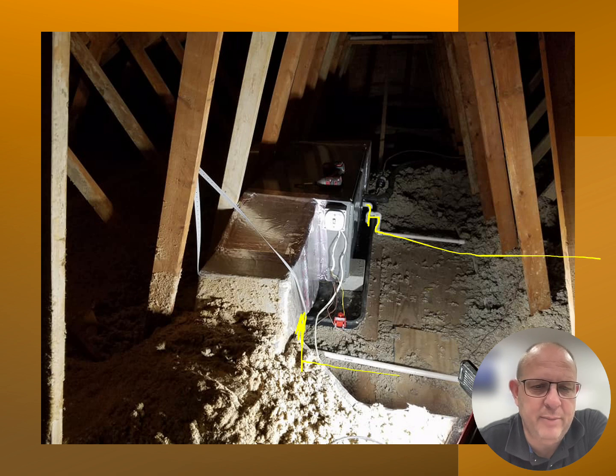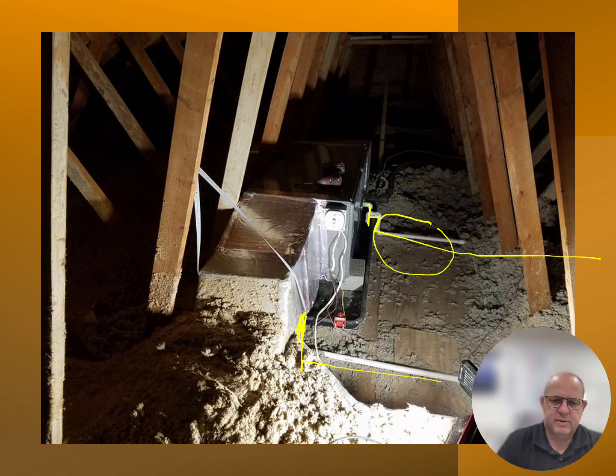The reason for this is if the primary drain does plug up and we have tied these two drains together, then the primary drain will overflow into the secondary drain, or the auxiliary drain pan, causing it to overflow in some way, shape, or form. So we want to take that condensate drain to a location where the customer will notice that the auxiliary drain pan has water in it and is dripping that water out. Now, this is going to save us from damage from the downstairs unit. I mean, the damage to the drywall that's underneath this unit, since it is an attic installation.